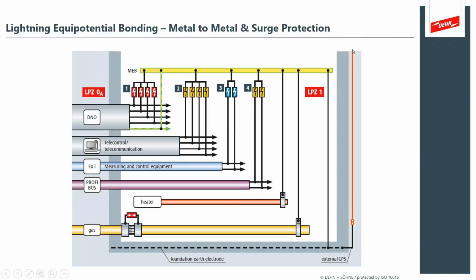And so in this diagram, we're seeing the bond to the earth electrode. It can be a ring, or the interconnected vertical rods. The lightning conductor coming down the side of the building, okay, that's the down conductor portion of this earthing connection. Notice it's separate from your metal works. You don't want that lightning into this gas pipe; it's separate, with its own dedicated connection. And pipe and metal works, of course, are directly bonded.